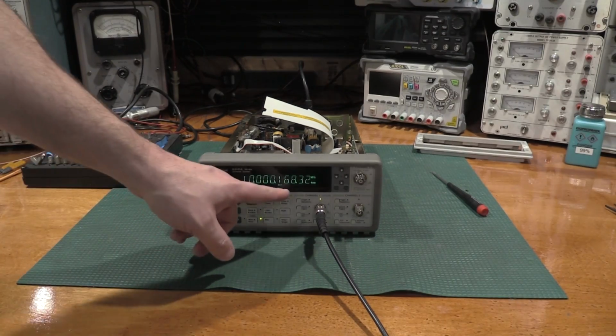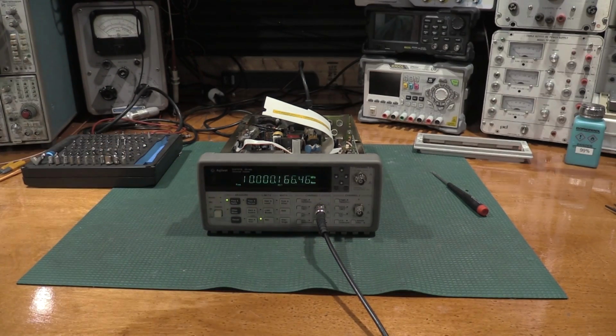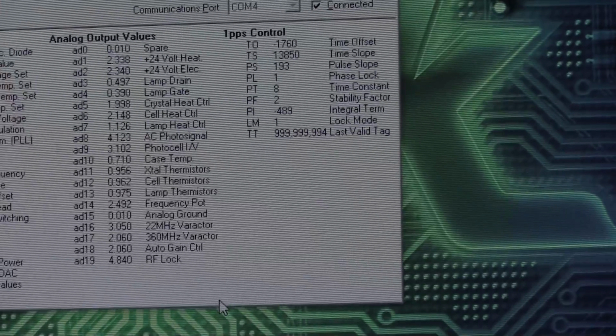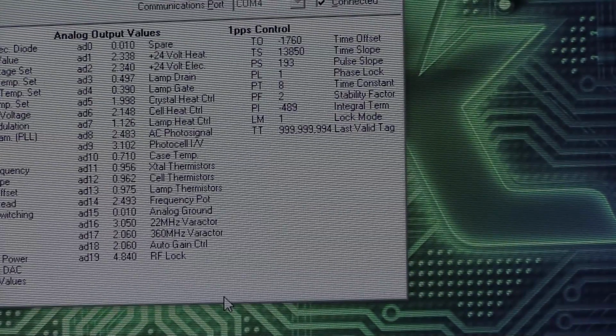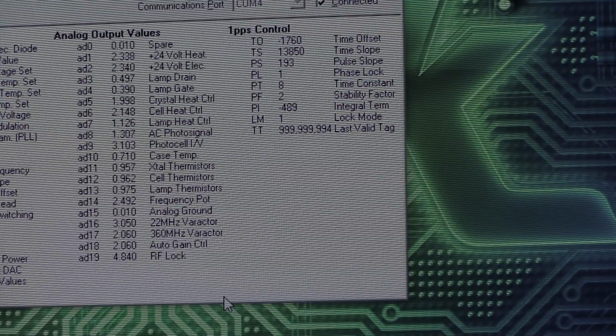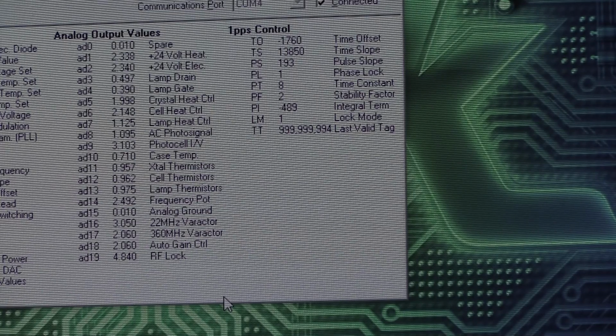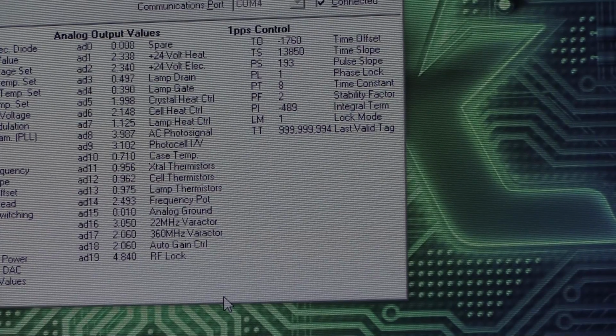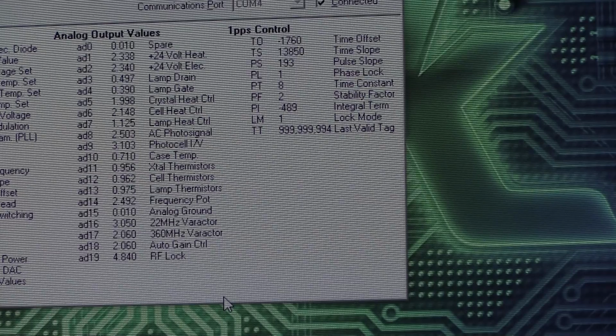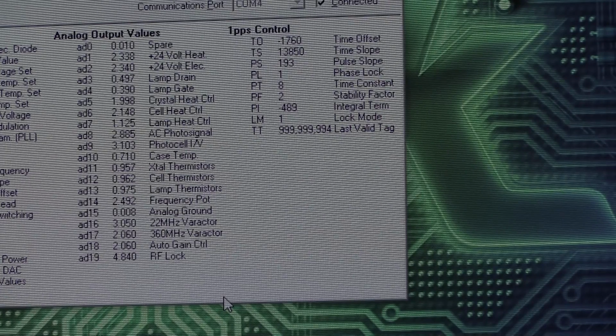All right, so we can see how far off it is. I have the rubidium standard plugged into the front end of the unit, and currently it's running about 6 nanoseconds slow. That last valid tag is, so it just servoed back. I was watching it a little bit ago, and it was dead even, so it's still dancing around there a little bit. And I go about plus minus 6 nanoseconds, so that is totally fine. But we are locked to the 1 pulse per second, and everything's good.